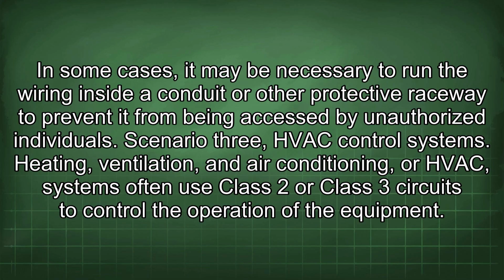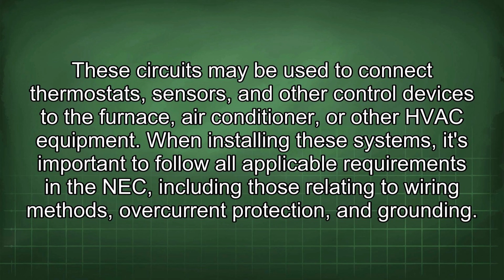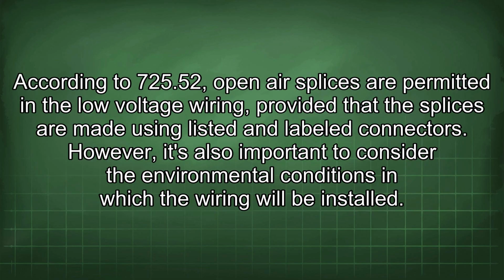Scenario 3: HVAC control systems. Heating, ventilation, and air conditioning, or HVAC, systems often use Class 2 or Class 3 circuits to control the operation of the equipment. These circuits may be used to connect thermostats, sensors, and other control devices to the furnace, air conditioner, or other HVAC equipment. When installing these systems, it's important to follow all applicable requirements in the NEC, including those relating to wiring methods, overcurrent protection, and grounding. According to 725.52, open-air splices are permitted in low-voltage wiring, provided that the splices are made using listed and labeled connectors.